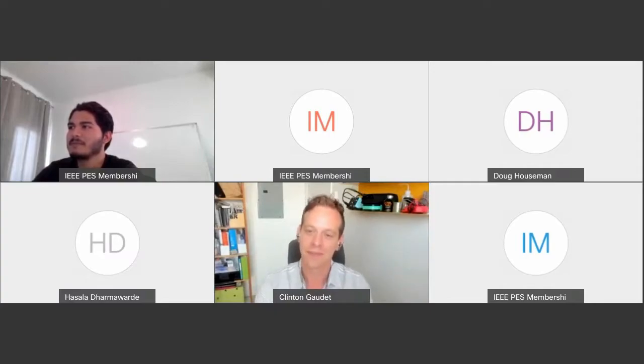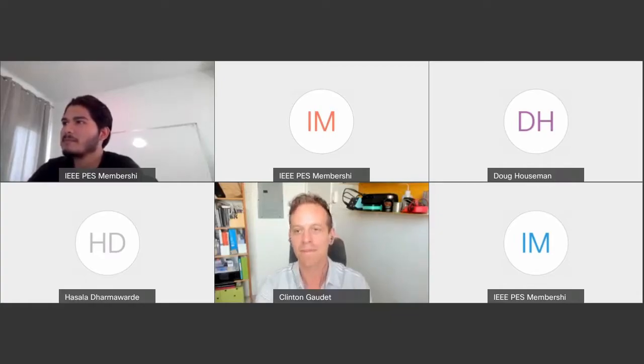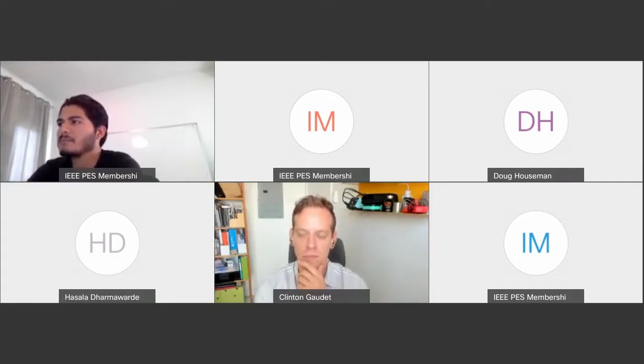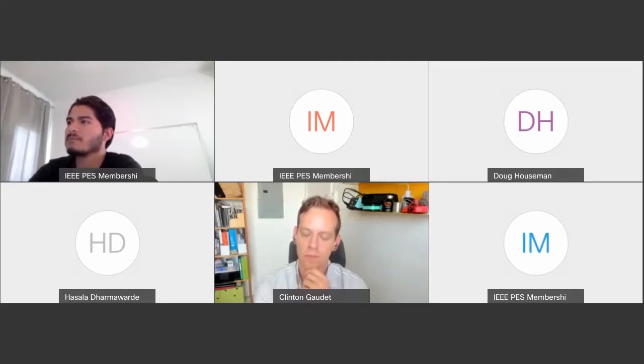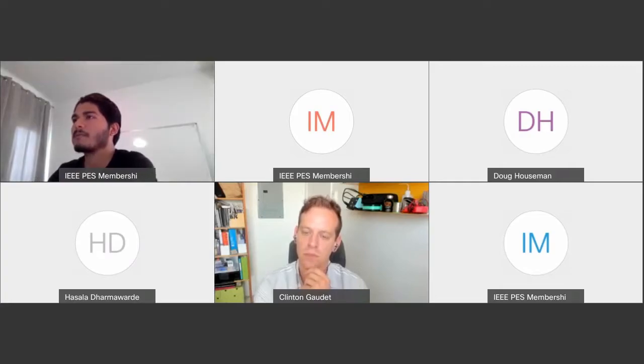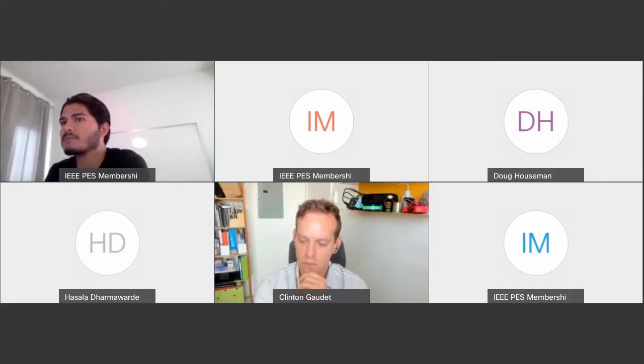Okay, so in a typical DC system, you both have a positive and a negative voltage, right? And let's just say we're using 1,000 volts, which is, until you get into HVDC for transmission, about the most anybody wants to work with in a factory or a commercial building. And in fact, if you look at the eMERGE standards, it's 380 volts for the higher voltage and 12 volts for the lower voltage for DC. But at 1,000 volts, running at full energy, you need to find enough energy in order to be able to drive that voltage down for a very short period of time using some sort of pulse.